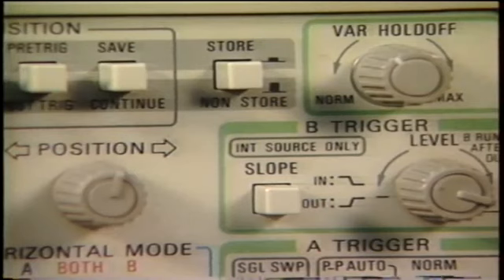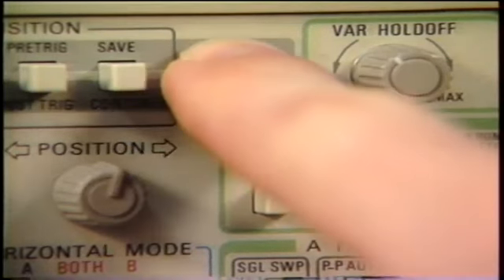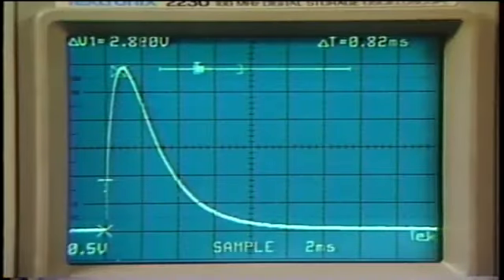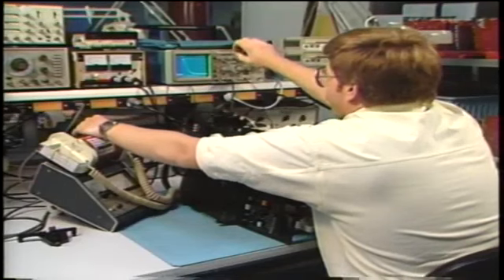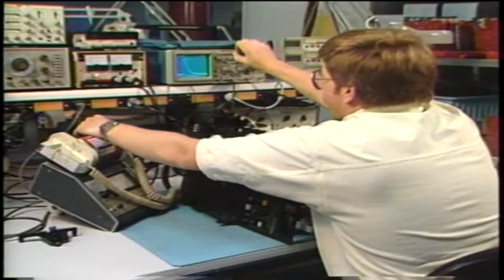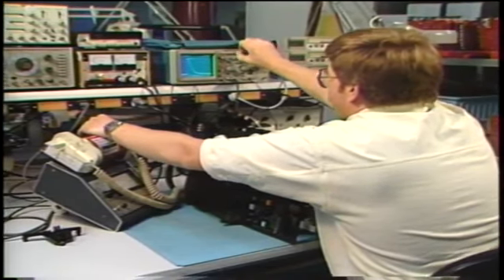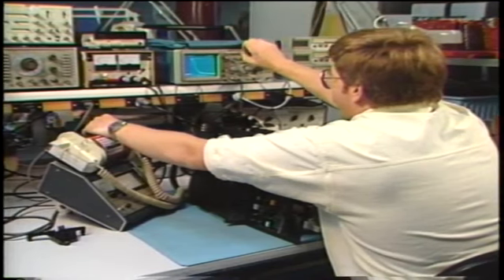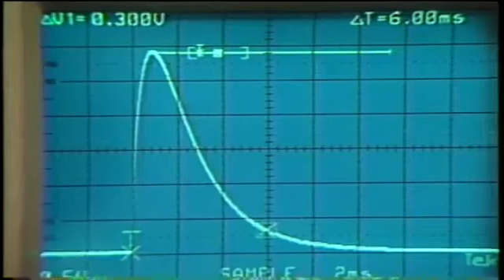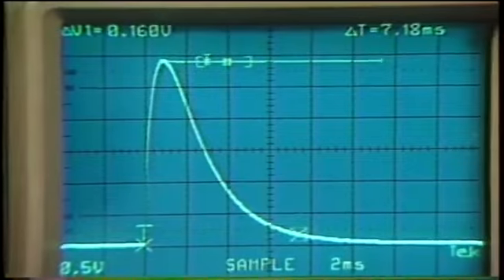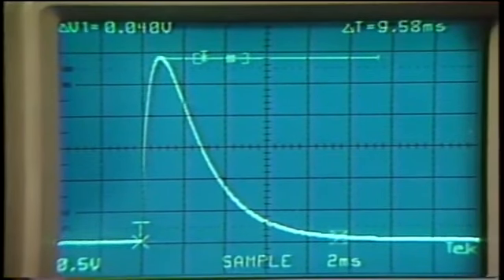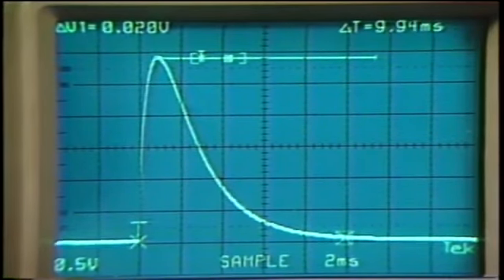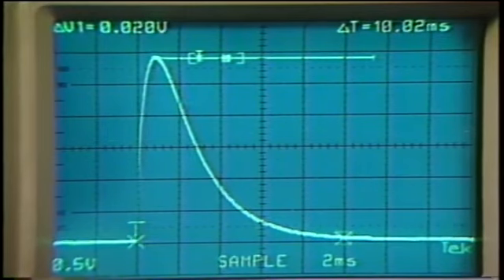The 2230 and 2221 combine digital storage with on-screen cursors and readout to make this difficult single-shot measurement with speed and accuracy. This is the final test area for this portable defibrillator. The single-shot output waveform must meet specifications for peak amplitude and residual amplitude after 6 milliseconds and 10 milliseconds. Note how quickly and accurately the cursors in the 2230 make these measurements.